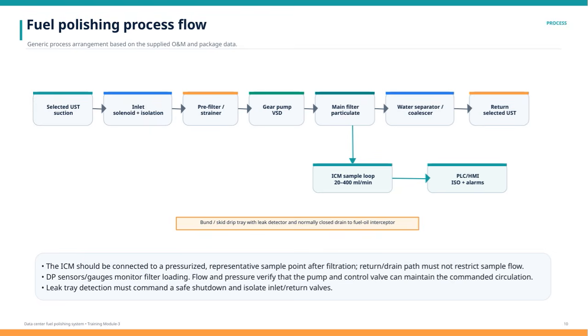After that, it goes through a pre-filter or strainer, which removes larger debris to protect downstream components. Following this, the fuel reaches the gear pump equipped with a variable speed drive, or VSD, which helps regulate the flow and pressure to match system demand. The fuel then moves through the main particulate filter, crucial for removing fine particles that could harm the engine or equipment. Water removal is handled next by a water separator and coalescer, ensuring any moisture in the fuel is effectively separated to prevent corrosion or microbial growth. From there, the fuel is returned to the selected underground storage tank, completing the circulation loop.